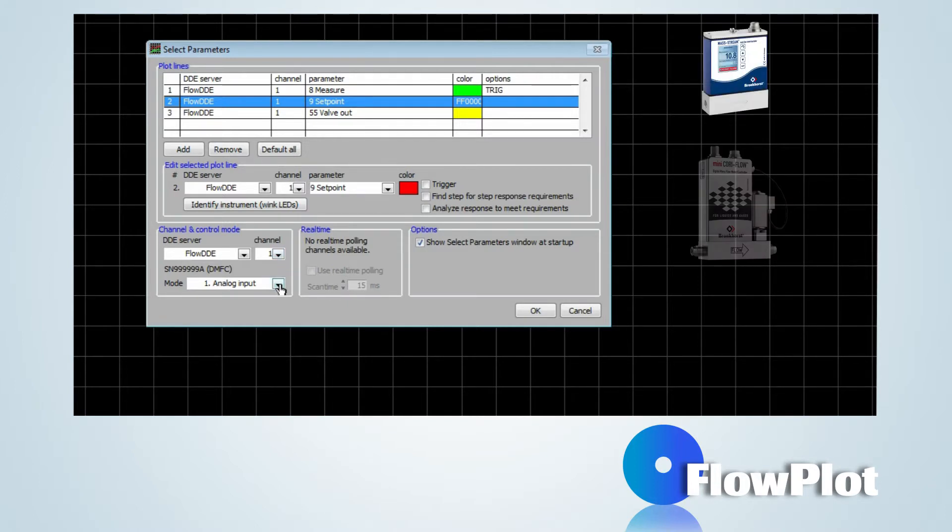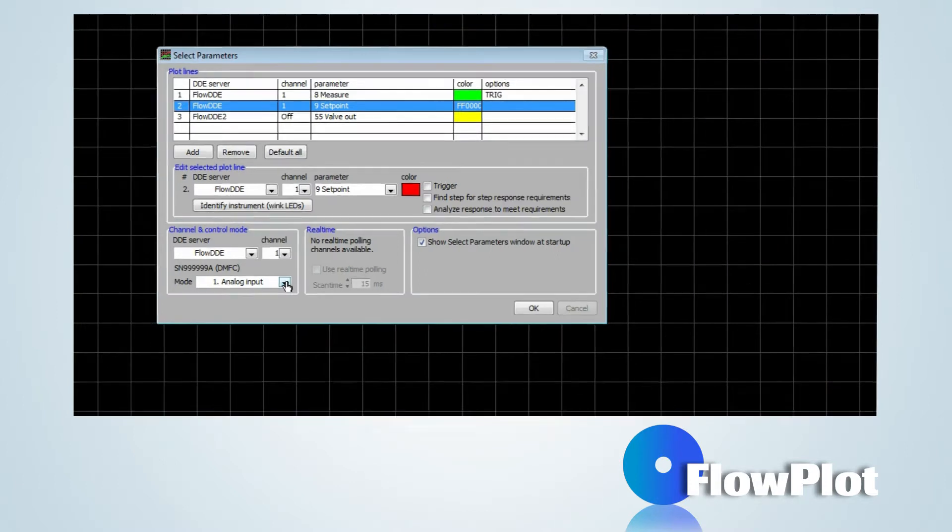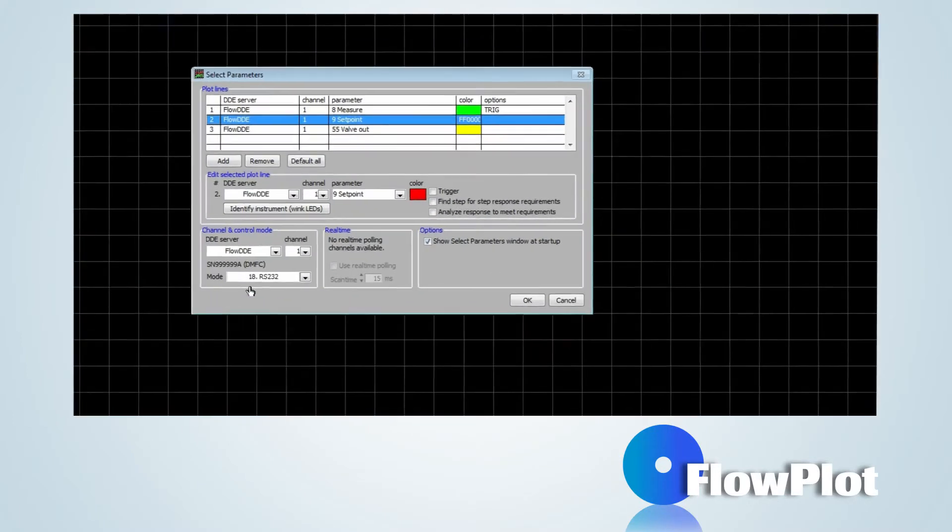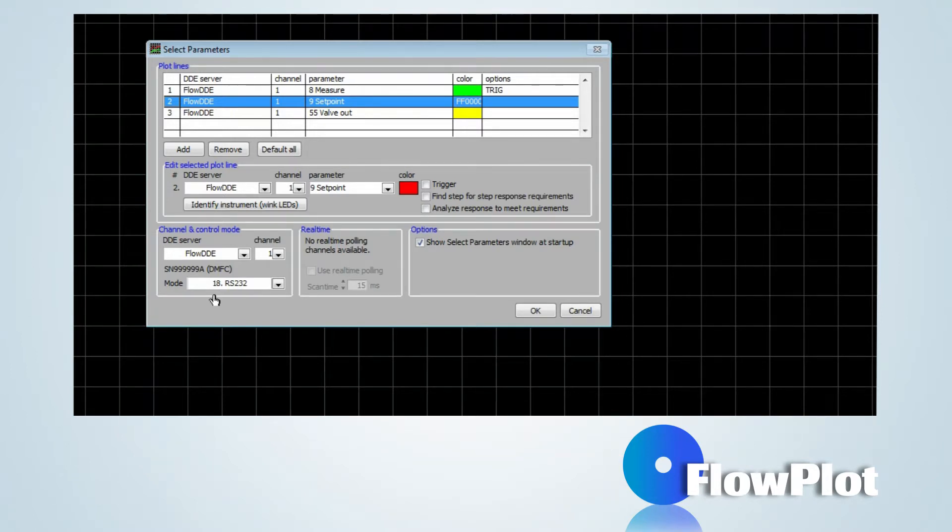In case of a digital mass flow controller, the setpoint can be adjusted via Flowplot. This is only possible when the control mode of the instrument has been set to RS-232. Now the instrument will accept a digital setpoint. Press the OK button to continue.